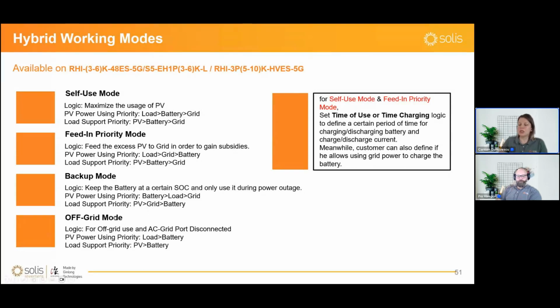And additionally, these inverters can also work in off-grid mode, but this means that they will never have any grid connection. So all your loads would be connected to the backup port. In this case, you would not even need a meter because you don't have a grid to connect to, and the system will work only based on PV and on the batteries.